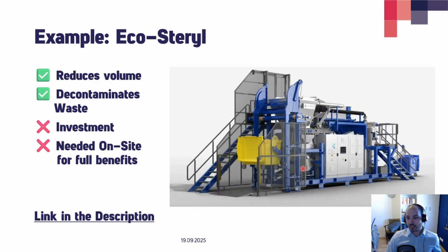It will all be shredded to bits, and then it will be transported in a cylinder where it's heated with microwaves to 100 degrees for 1 hour, and that achieves sterility. So you sterilize it using lower temperatures and longer times, and the plastics do support that better than harsh steam sterilization that is very short, very hot. And then in the end, you will have these pellets, and these pellets can then be washed with an additional washing step, or can be sorted with an additional sorting step.